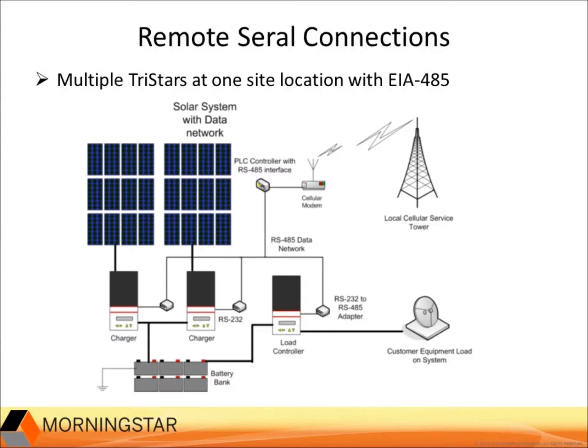In this example, Morningstar's RS-232 to EIA-485 adapter is used to network all of the TriStars to the same EIA-485 network, and the PLC controller polls each TriStar according to its Modbus ID. You can also create a PC connection to the EIA-485 network and address each one with MSView.